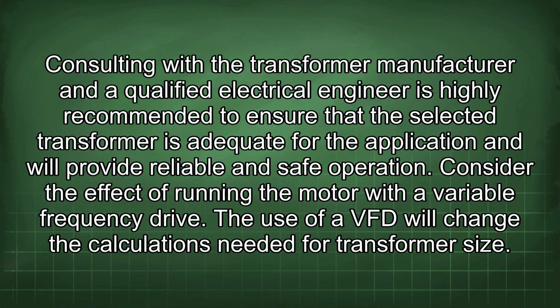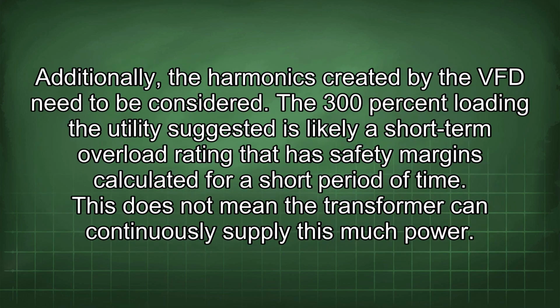Consider the effect of running the motor with a variable frequency drive. The use of a VFD will change the calculations needed for transformer size. Additionally, the harmonics created by the VFD need to be considered. The 300% load the utility suggested is likely a short-term overload rating that has safety margins calculated for a short period of time. This does not mean the transformer can continuously supply this much power.